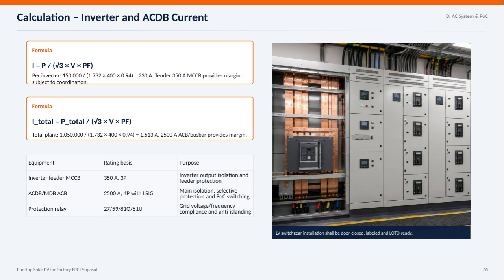The inverter feeder MCCB for isolation and protection at 350 amps, the main ACDB or MDB ACB at 2,500 amps with LSIG for switching and selective protection, and protection relays for grid compliance and anti-islanding. Finally, it's important that all low-voltage switchgear installations are door-closed, properly labeled, and ready for lockout-tagout procedures to ensure safety during maintenance.